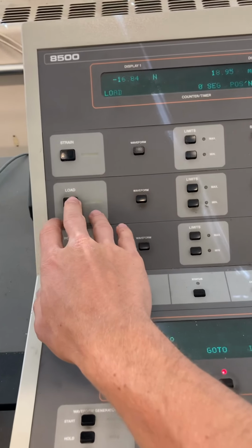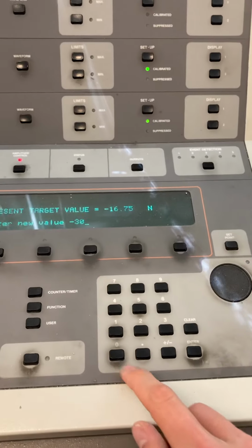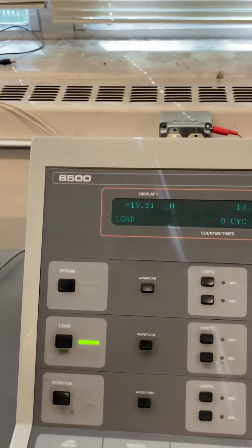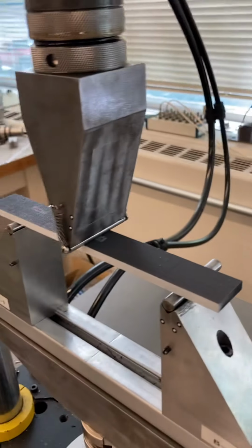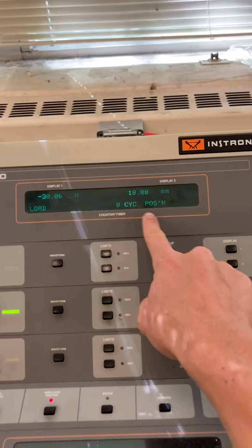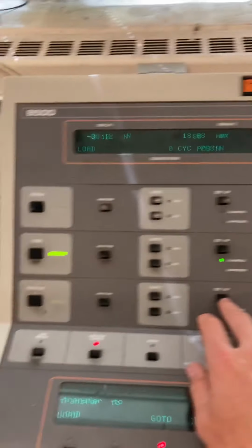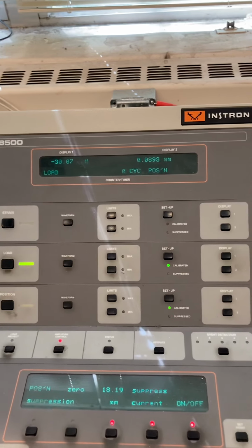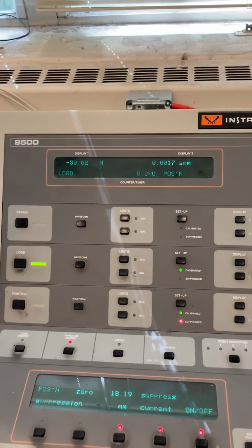There you can see the load changing now. What I like to do is go to load. I like to do a minimum load go to of 30 newtons, negative 30, enter. Should pop to 30 newtons, right on there, it'll look good. Then what I like to do is zero out the position at this point. So to set up under the position, then we'll go to suppress current. So it starts to blink, the position changes. That's good, okay, it looks good.